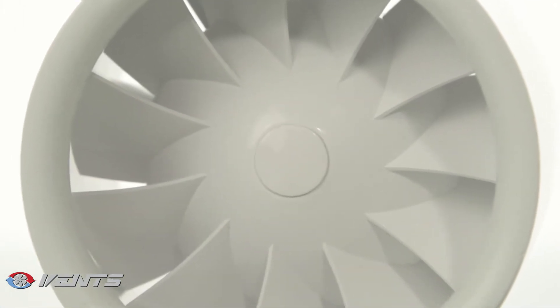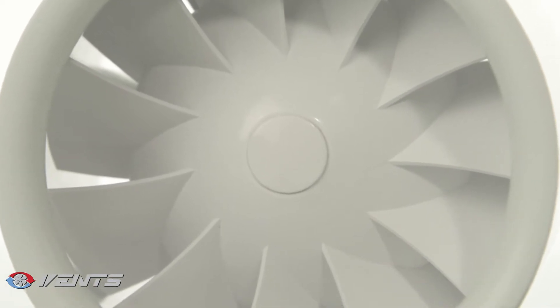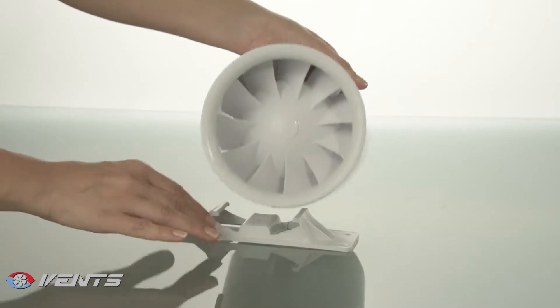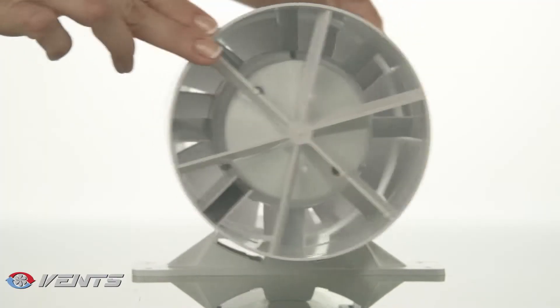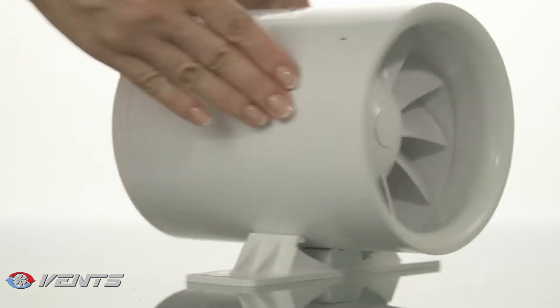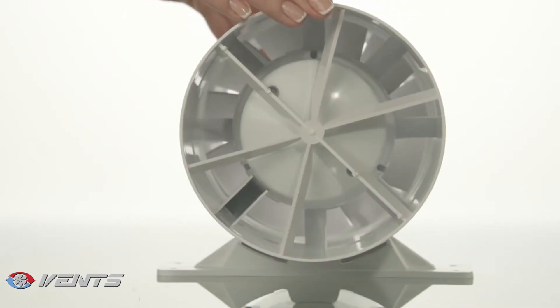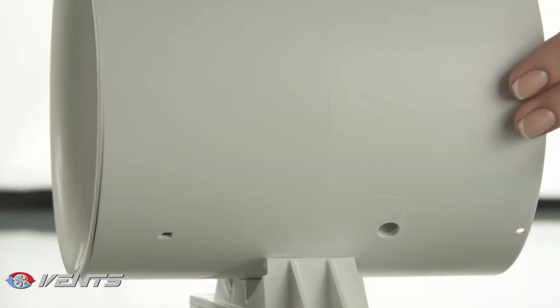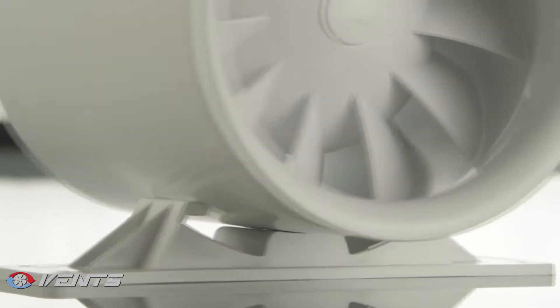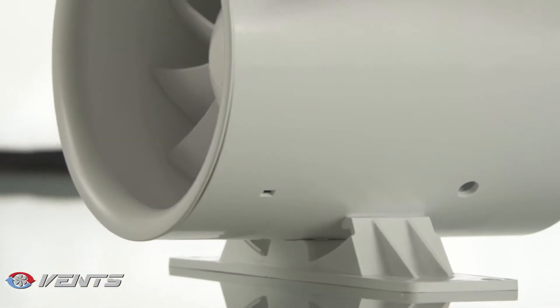The new fans feature an improved impeller for higher efficiency at the same near-silent noise level. Vents QuietLine fans are equipped with reliable motors which run on ball bearings with a minimum power consumption of 4.5 Watt. The motors are installed on rubber-damping inserts, which absorb motor vibrations and ensure silent operation of the fans.